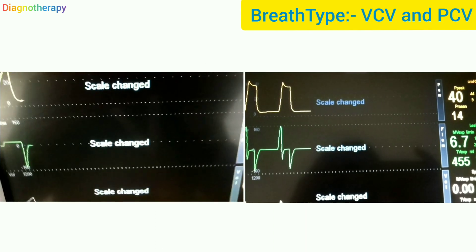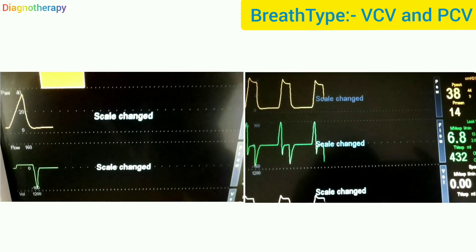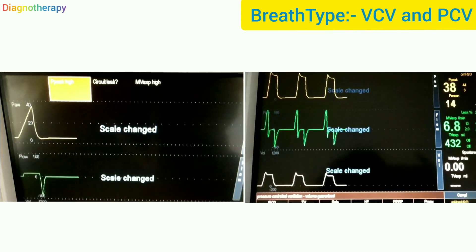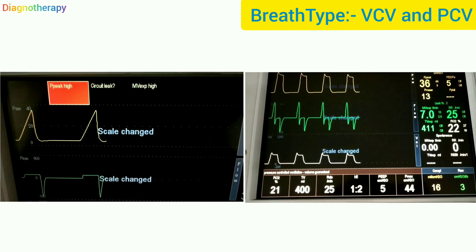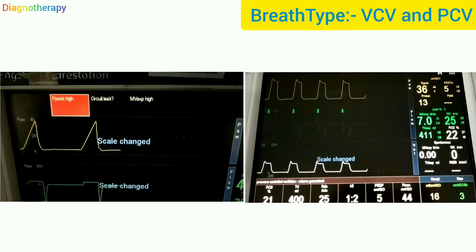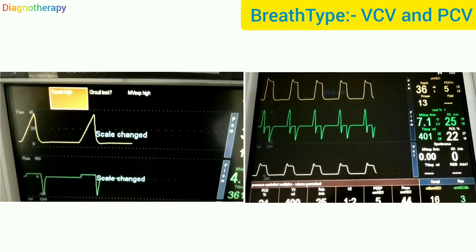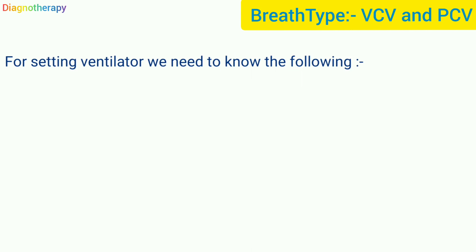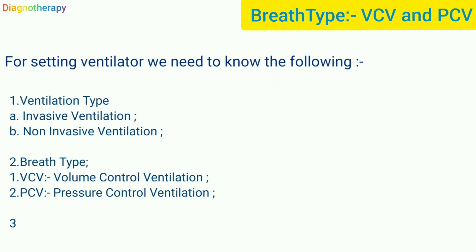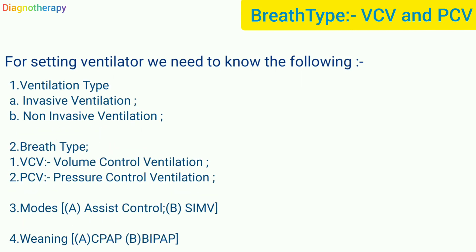Let's have a look at the ventilator screens. On the left it is volume control ventilation and on the right it is pressure control ventilation. For setting a ventilator we need to know the following: first the ventilation type, second the breath type.